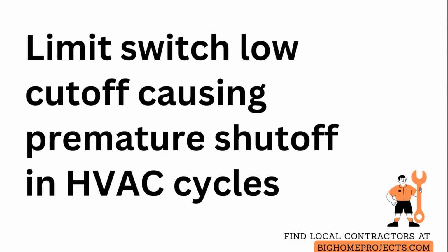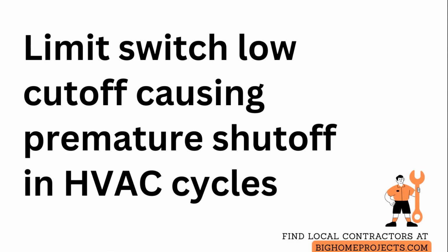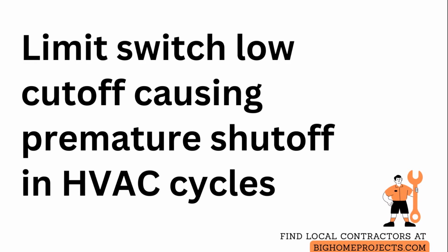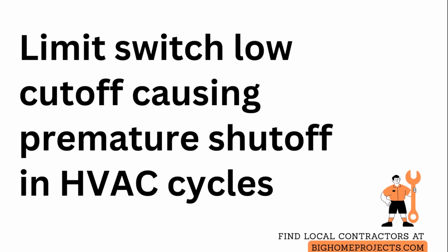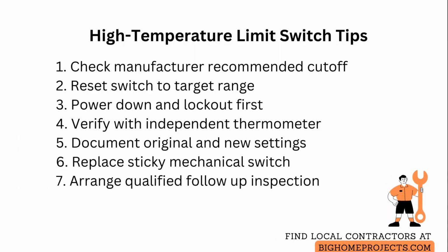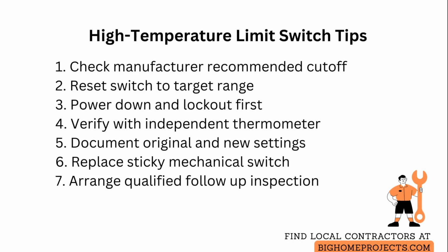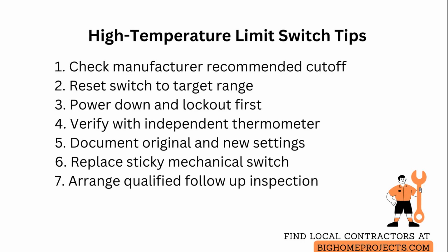A high temperature limit switch set too low can cause premature shutoff that prevents systems from completing required cycles and can damage equipment or safety controls. When a limit switch cuts off too early, the system cannot reach the temperatures needed for proper processes, and this creates incomplete cycles and reduced efficiency.